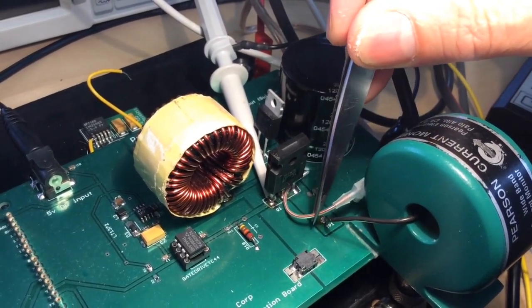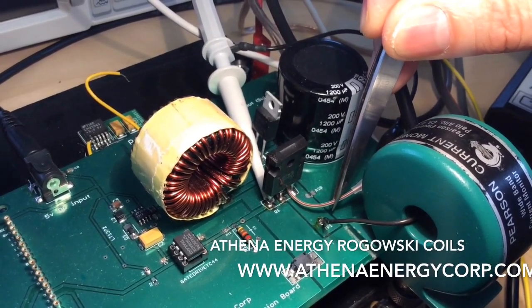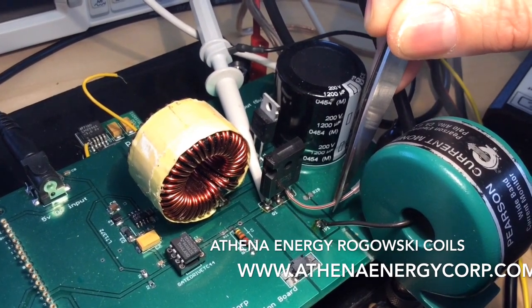Inserting the Rogowski coil even this far, about 10% of the length, is going to still give you about 1% accuracy in current measurement.